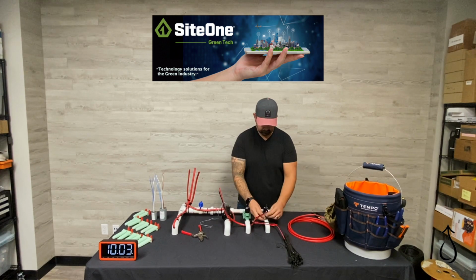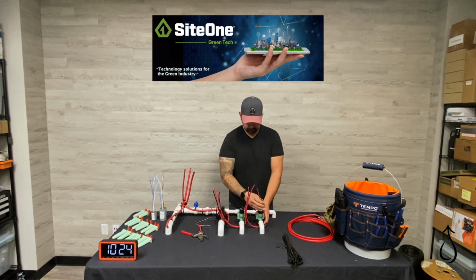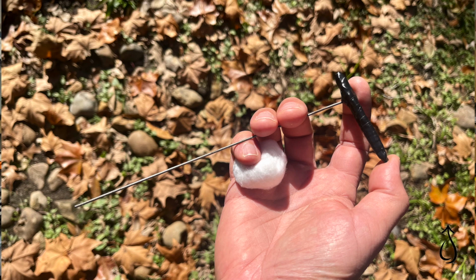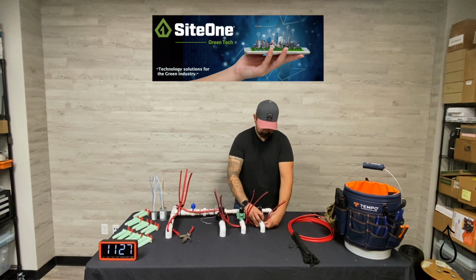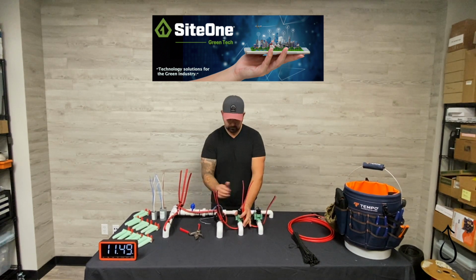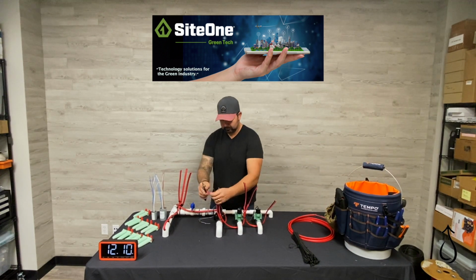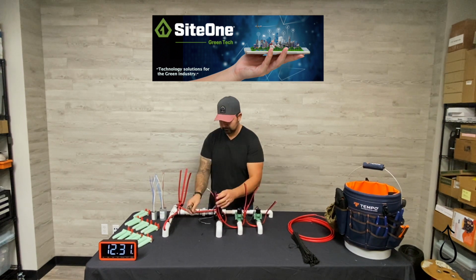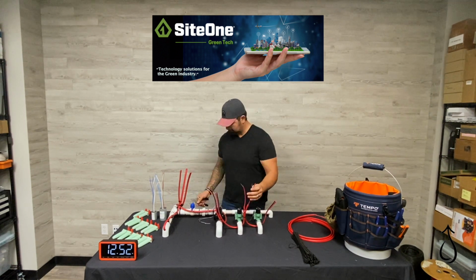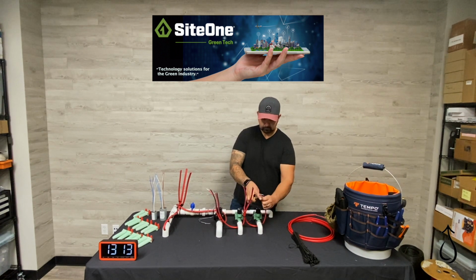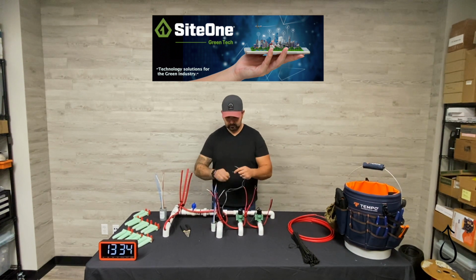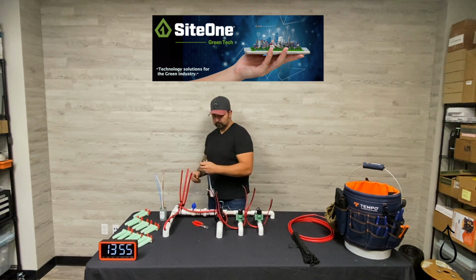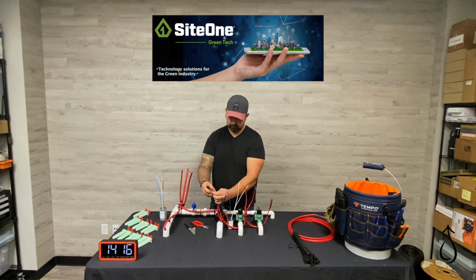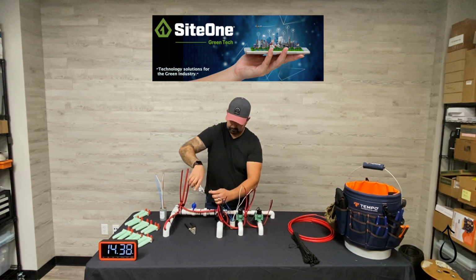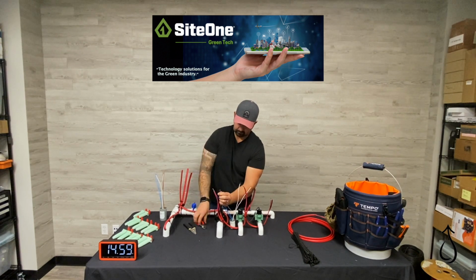After the wire nuts are installed, I will move on to the DBRY6 caps. 2 critical details here are my push tool and a bag of cotton balls. Every time I install a DBRY6 cap, I like to place a cotton ball near my pinky while holding the new DBRY6 cap. Then I will grab the push tool with my other hand and let the dry wire nut simply touch the dielectric grease within that cap. With the dry wire nut only touching the grease, I will use this push tool to fully insert the dry wire nut in the DBRY6 cap, keeping those wires dry.